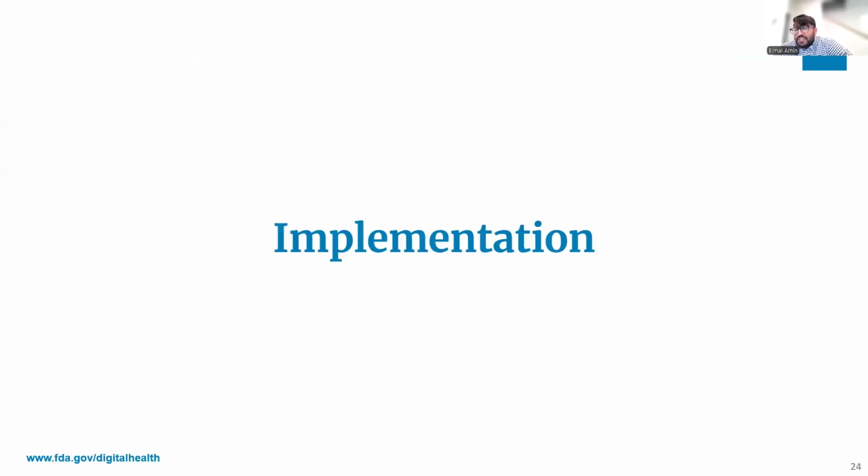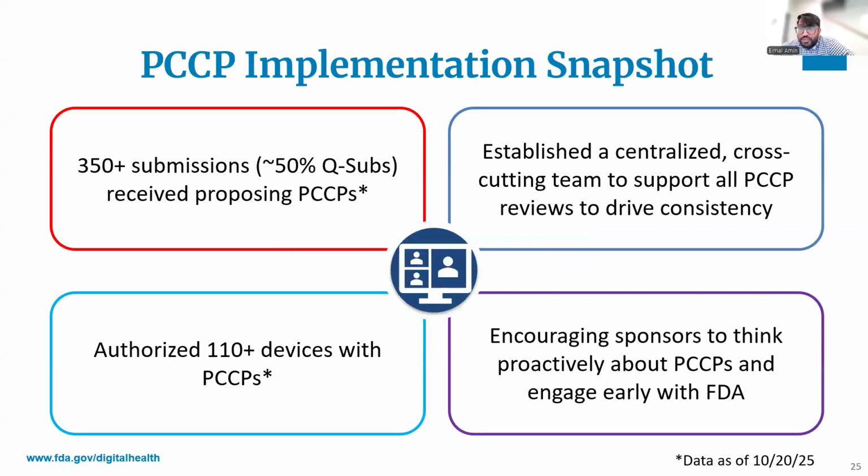So to give you guys a snapshot of the current numbers of PCCPs that we've had in-house. As of October 2025, FDA has received more than 300 submissions proposing PCCPs, and roughly half of those were pre-submissions or Q-submissions. We've authorized more than 110 devices with PCCPs, and we've established a centralized cross-cutting team dedicated to PCCP reviews to drive consistency. You can expect that it will be reviewed by people who have deep expertise in the specific area and who are applying consistent standards across all submissions.